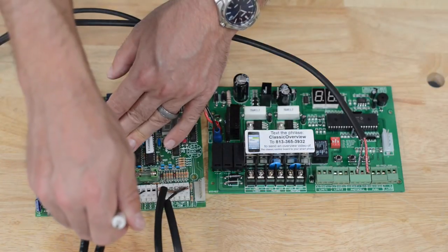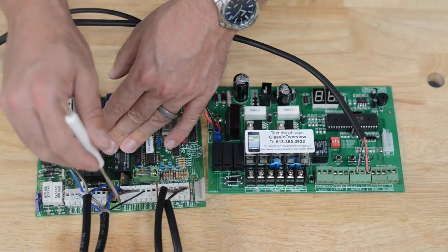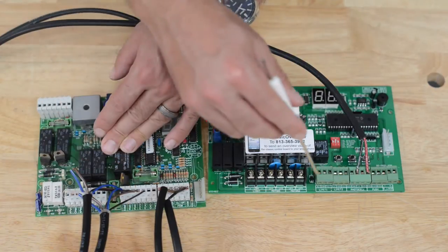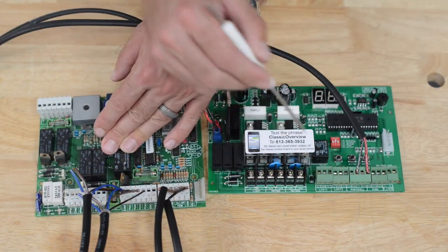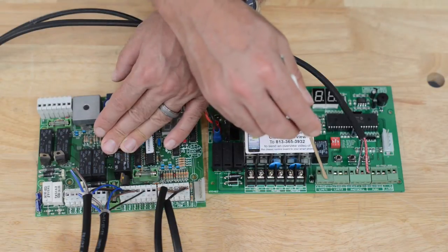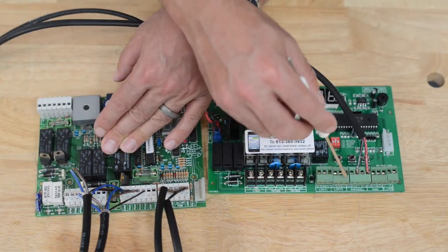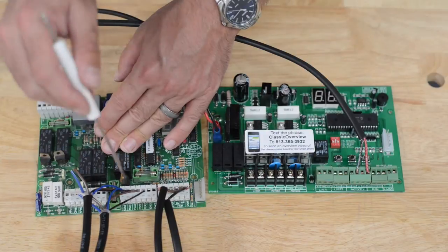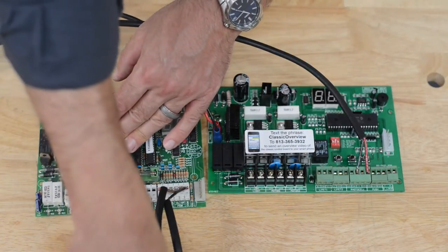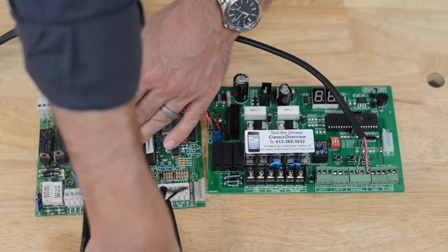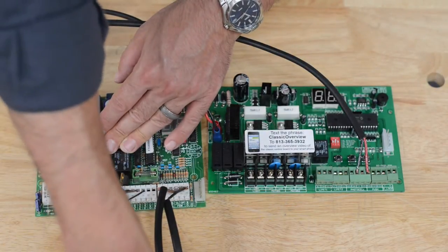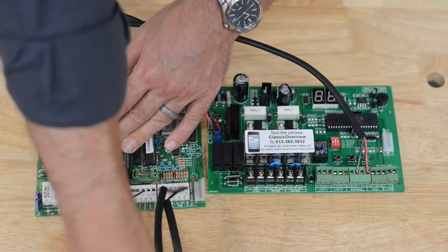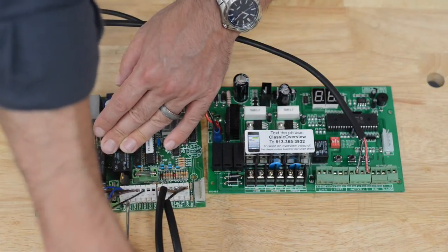In this first terminal, which is COM-F, the COM-F is going to be the center terminal on either of these two limit switch blocks. Limit one gets paired up with motor one. Limit two gets paired up with motor two. So we're going to remove the wires for motor one first. I loosened COM-F and now I'm going to take out FCC1 and FCA1.